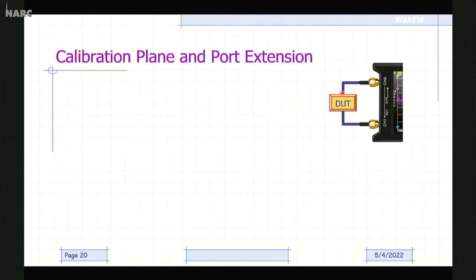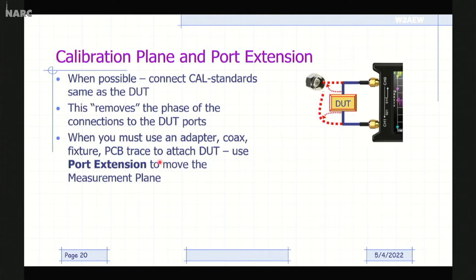So when it's not possible to do that, you can run a calibration at the end of whatever you can get to, as close as you can get to the device, and then apply something called a port extension, okay, to account for the additional phase and delay with the additional connection that you weren't able to calibrate out, okay? So again, this is when you must use some kind of an adapter or coax or fixture to connect up to your DUT, because your DUT might be at the end of a transmission line trace on a circuit board, right? So the port extension can be used to remove that.